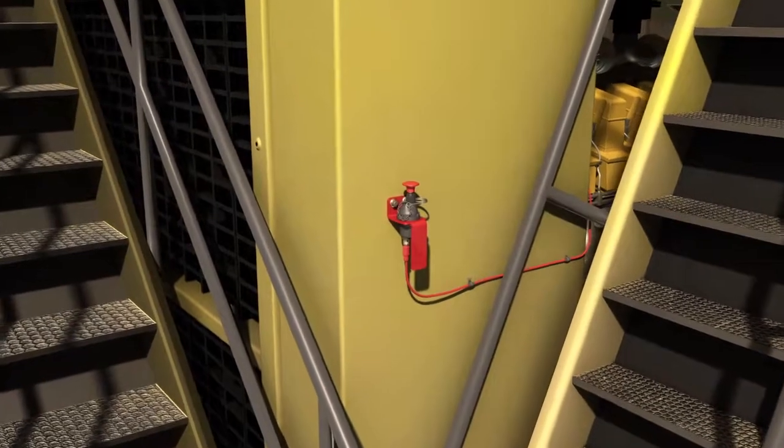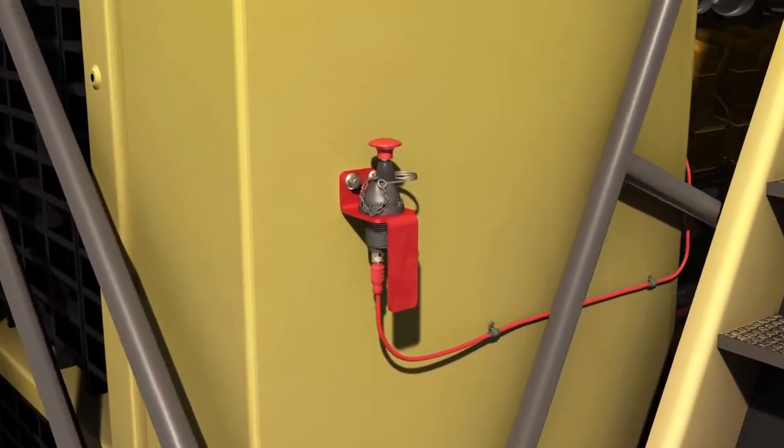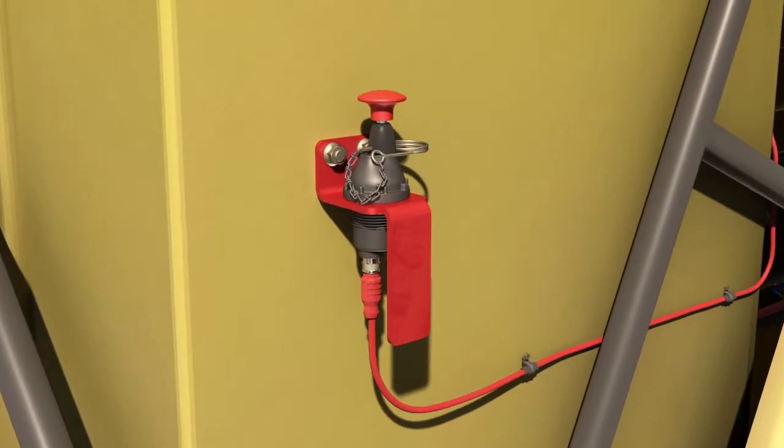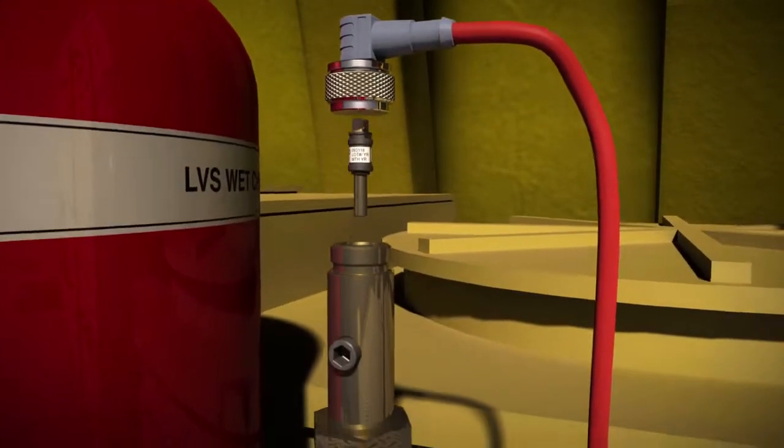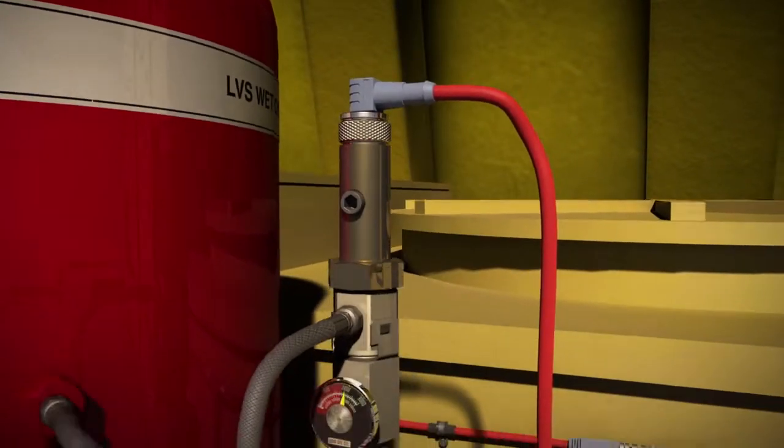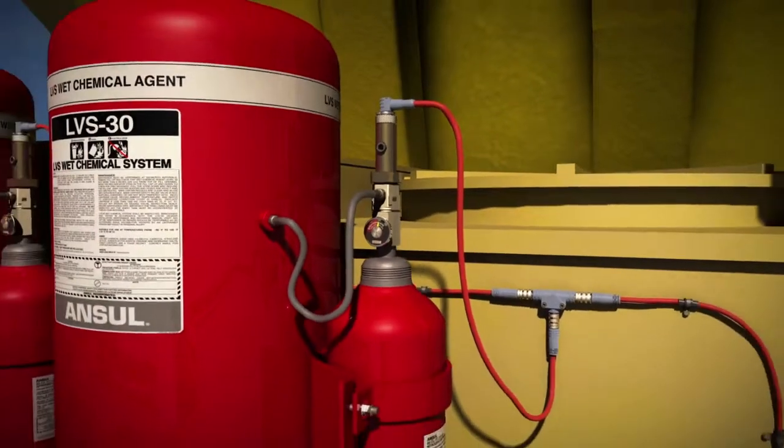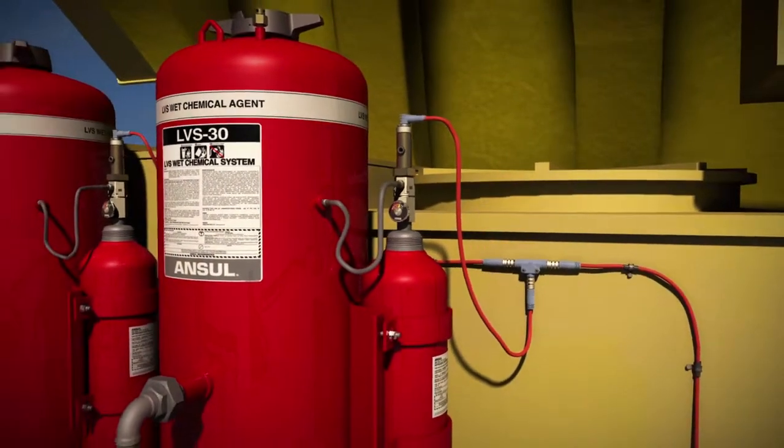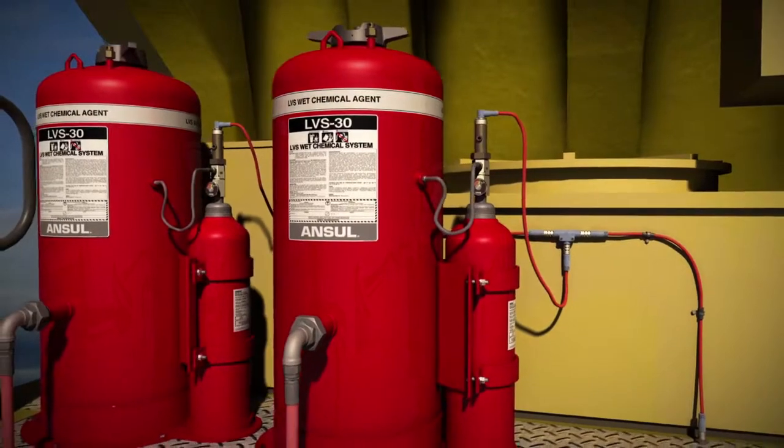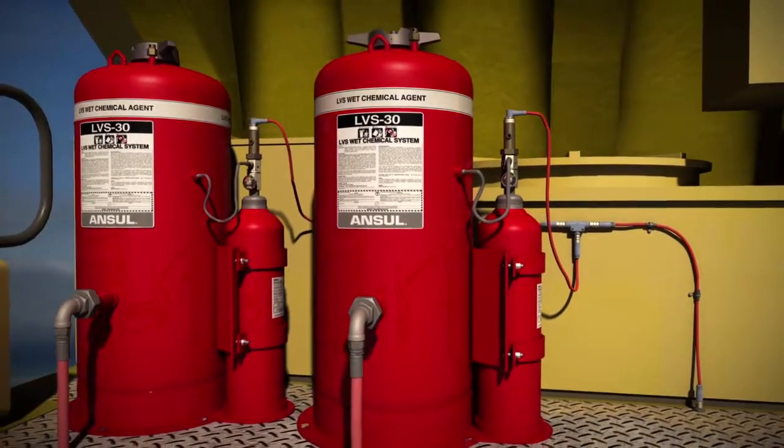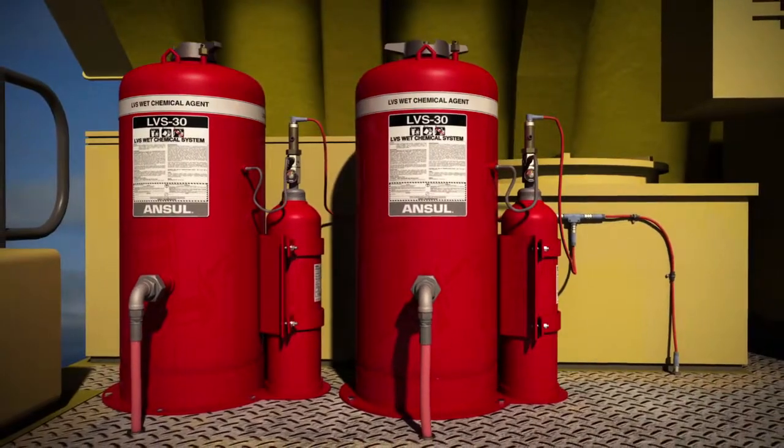The electric manual actuator provides an additional means of remote manual actuation and is located along paths of egress. The pyrotechnic actuation device is installed in the electric pneumatic actuator which is mounted on the expellent gas cartridge located near the agent tank. The release circuit provides supervision from the CheckFire 210 system to the electric pneumatic actuator and can actuate a maximum of 10 electric pneumatic actuators.